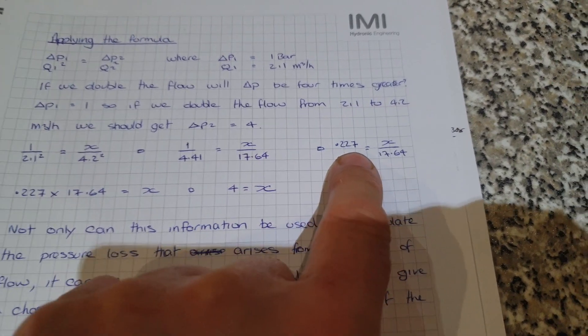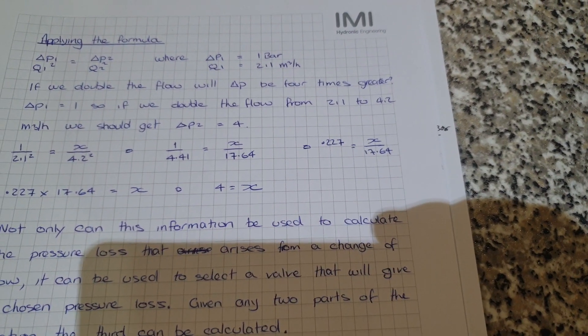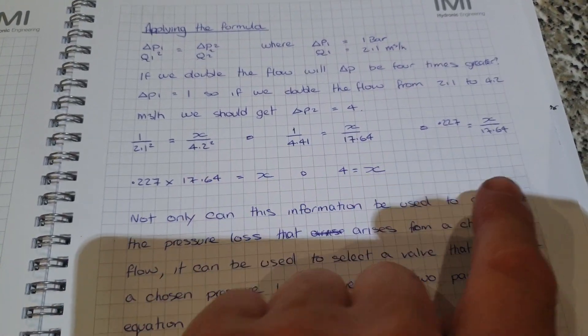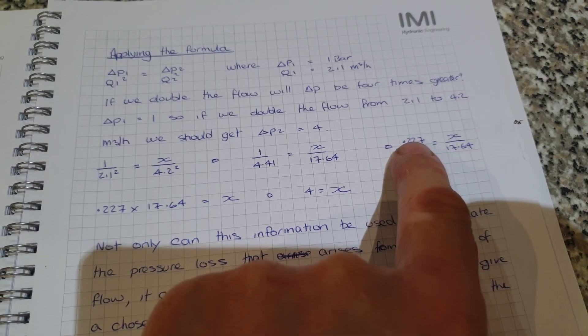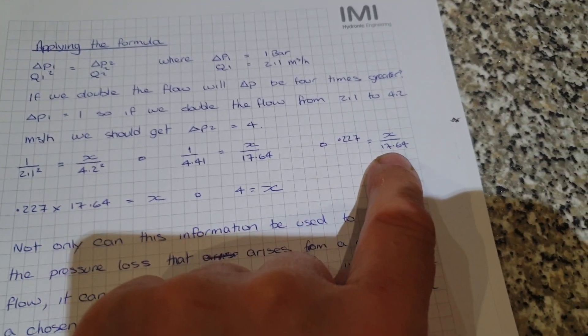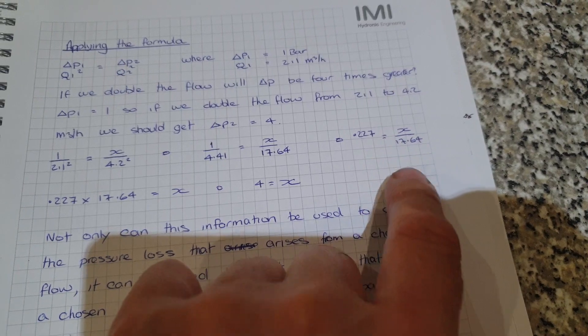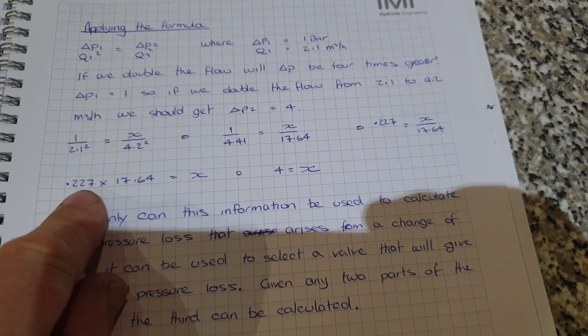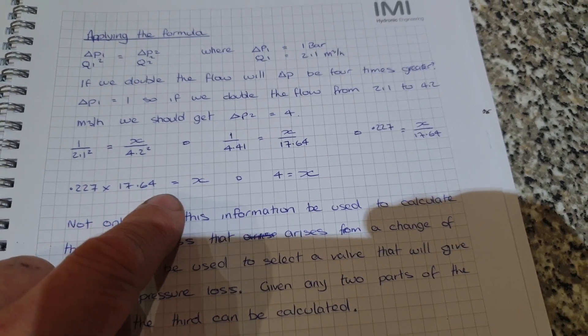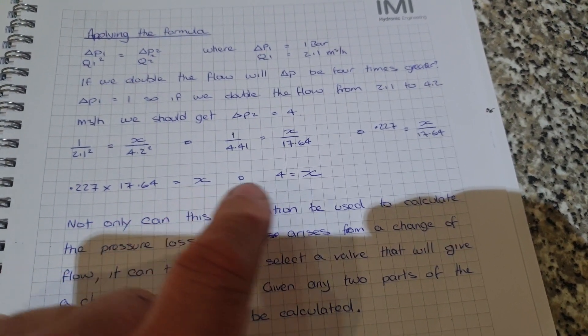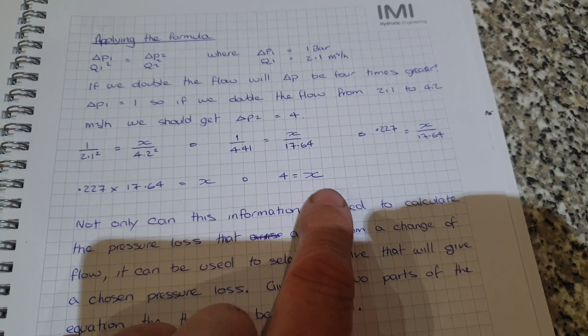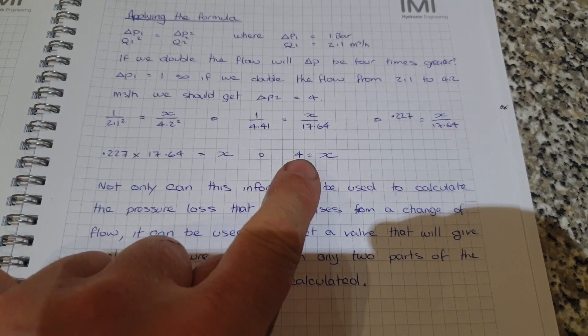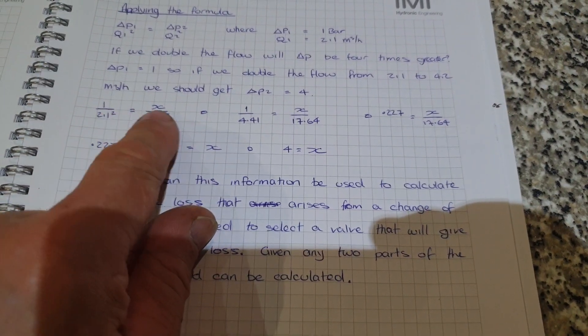Then we will divide 1 by 4.41, so that comes to 0.227 equals X divided by 17.64. We then multiply both sides by the division side of this one, which cancels it out or moves it across, giving us 0.227 times 17.64 equals X. If we do the maths there, we come to an answer of 4. So X is equal to 4, which means that if we double the flow, we get 4 times the delta P, proving the formula to be correct.